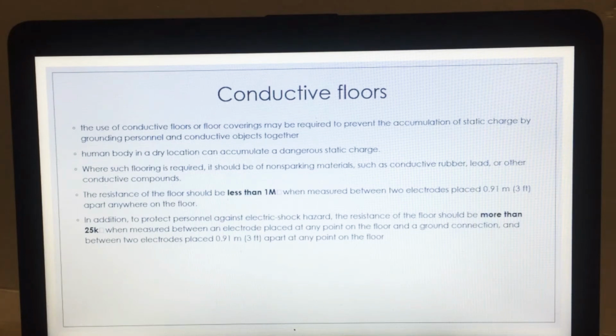By grounding the personnel and conductive objects together, a human body in a dry location can be prevented from accumulating a dangerous static charge. Where such flooring is required, it should be of non-sparking material such as conducting rubber, lead, or other conductive compounds. The resistance of the floor should be less than 1 megaohm when measured between two electrodes placed 0.91 meter or 3 feet apart anywhere on the floor.